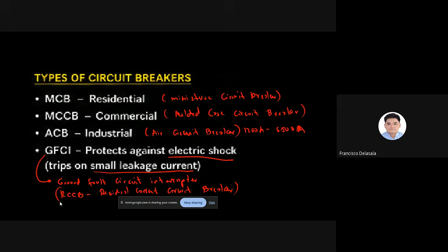So the other term for GFCI, because ang GFCI po yung pinaka-common term natin because we are following the Philippine Electrical Code. So the Philippine Electrical Code, ang kanyang tawag sa ganitong klaseng overcurrent protective device is GFCI. But sa Europe, the term for this type of device is an RCCB or residual current circuit breaker. Yeah, so residual current breaker. So either of those two is the same device. So they will protect against electric shock during a ground fault or a leakage current.